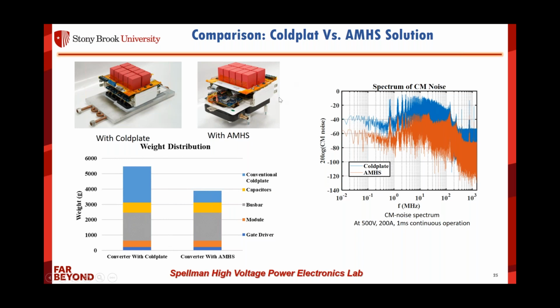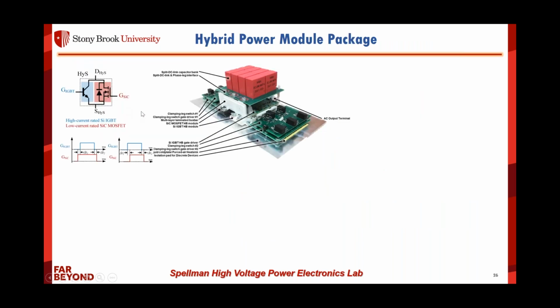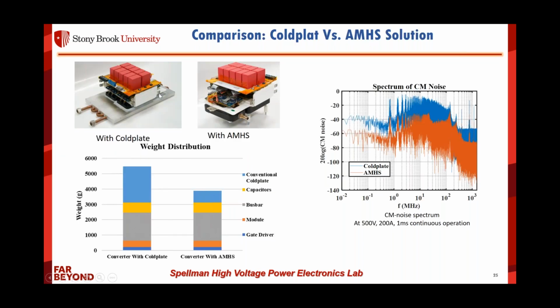Right on top of that, once I replace my off-shelf cold plate, which is the aluminum piece, with the additive manufactured plastic 3D printed cold plate, this is the footprint. The top module here is exactly the same as what we have, but the bottom side is much more reduced. And with that, we're seeing a weight reduction of more than 1 kilogram from removing this heavy metal piece.